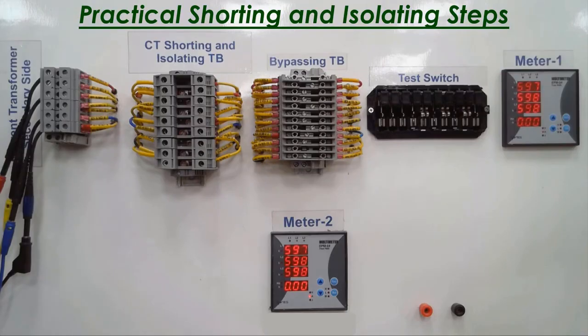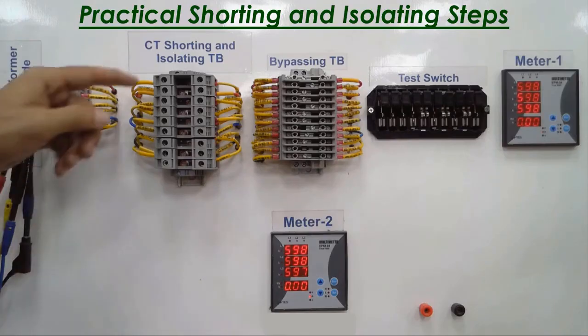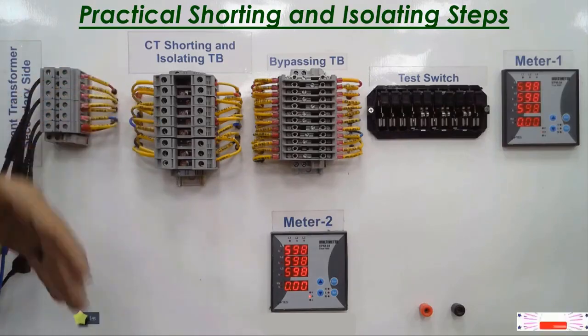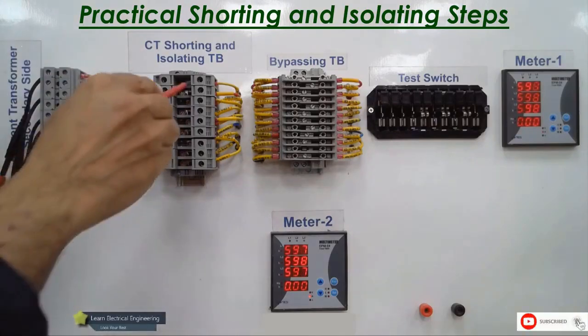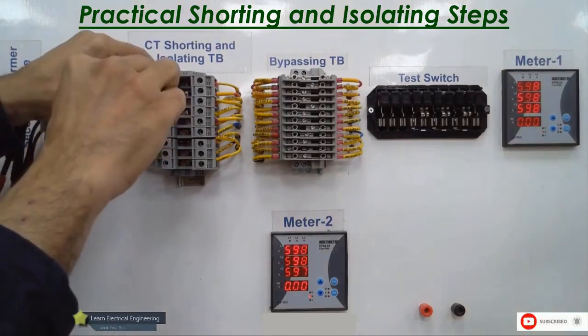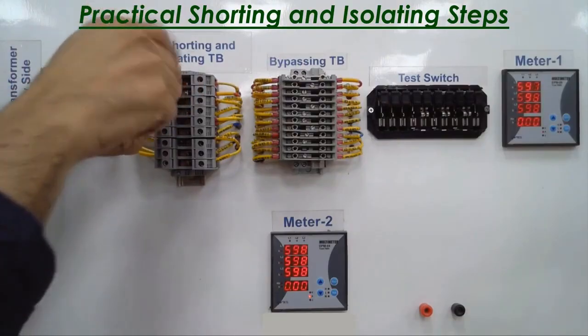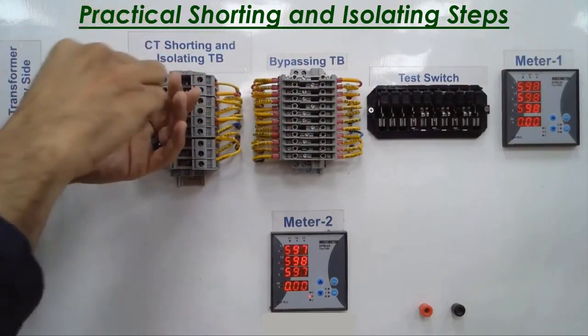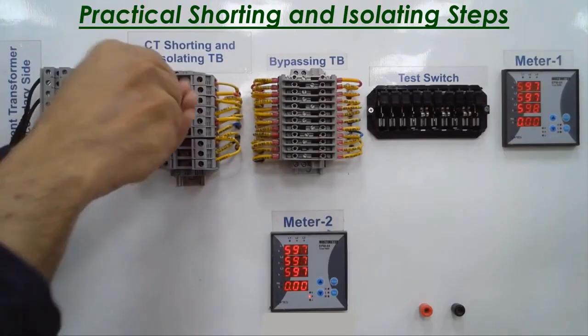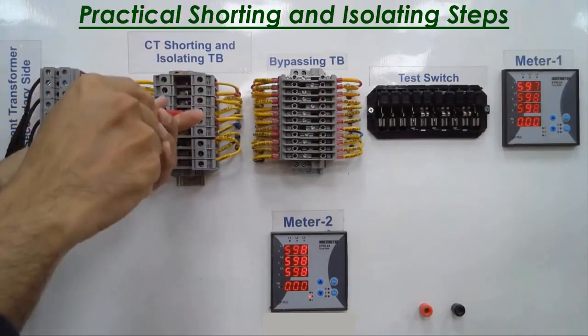Very good. As for the shorting process, we agreed that you will do it by first closing 1, 3, 5, and 7, and then opening 2, 4, 6, and 8. So I start by bringing link number 1 on the left and make sure everything is in order. Then I have terminal number 3, followed by terminal number 5.